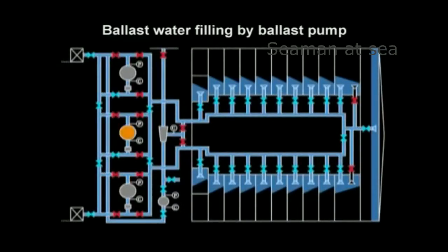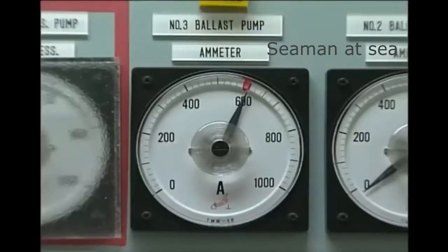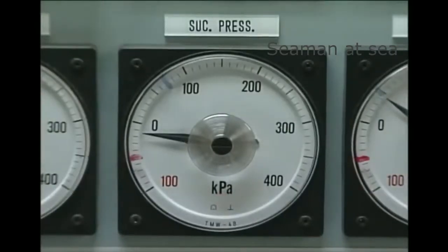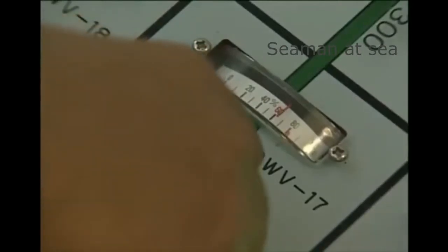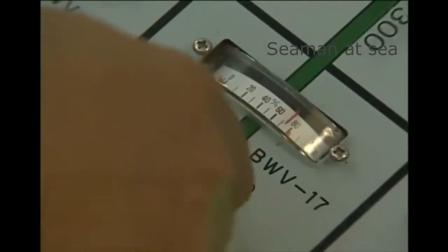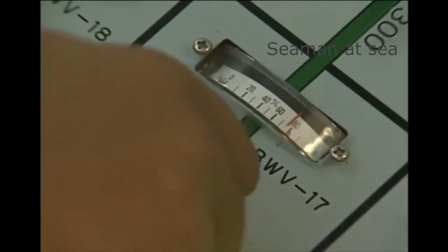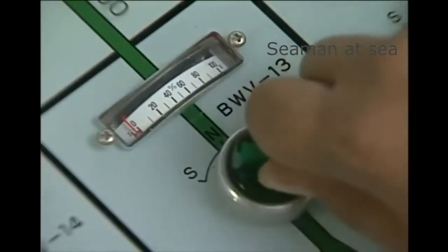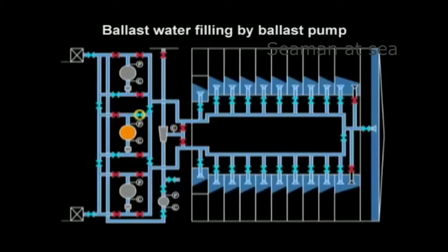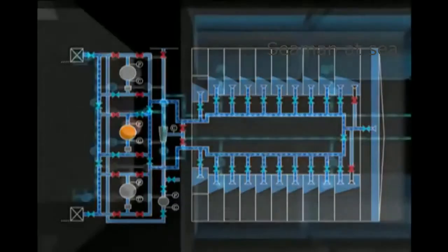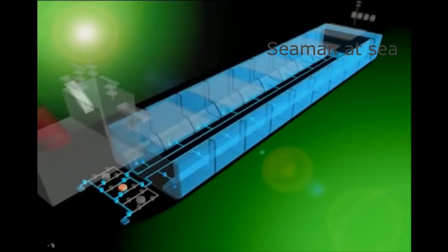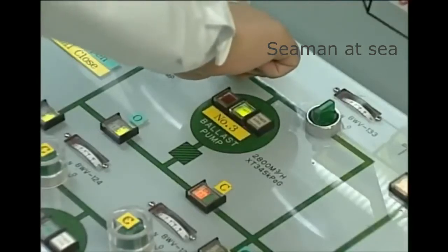Start the ballast pump. After the pump has been started, check the ballast pump electric current value, discharge pressure, and suction pressure. When changing ballast tanks for filling, open the tank's suction valve to be filled next, then close the suction valve attached to the ballast tank that has completed filling. When filling of all tanks has been completed, stop the pumps by closing the ballast pump discharge valves, then close the tank's valves.